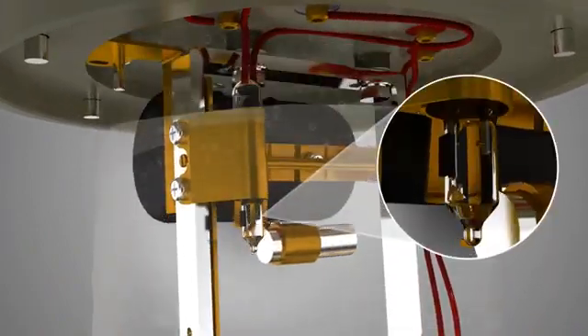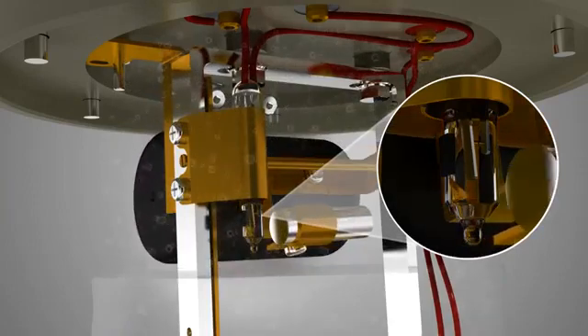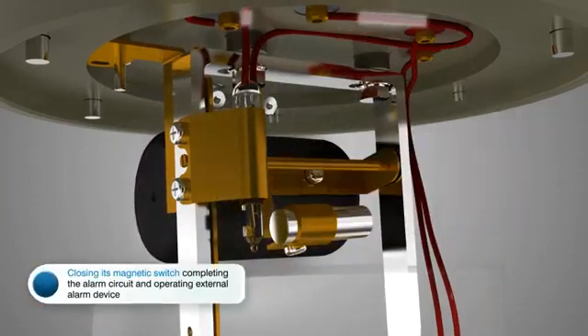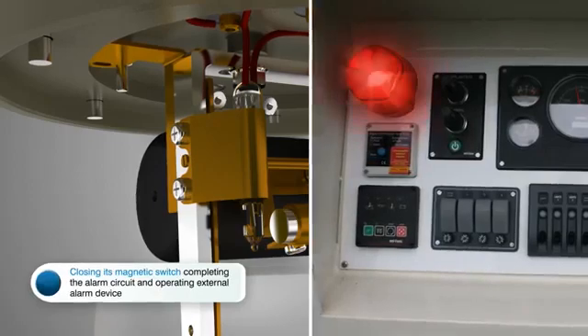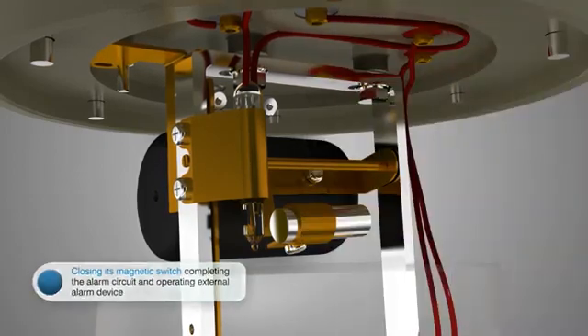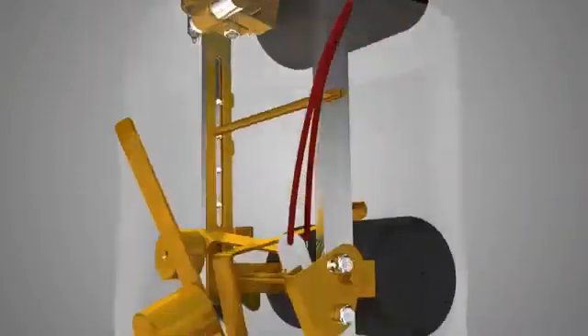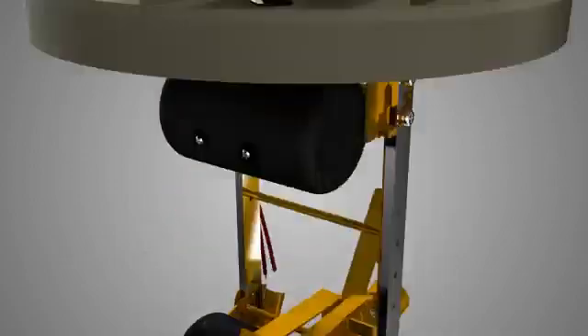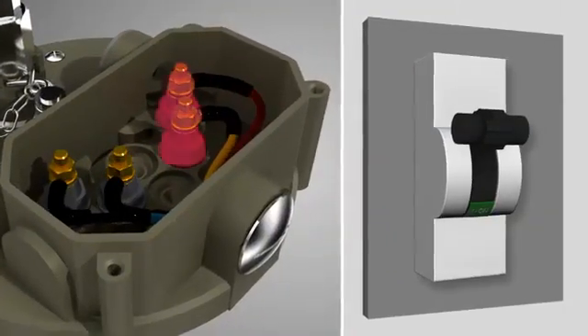The upper float falls down along with the oil level, closing its magnetic switch, thus completing the alarm circuit and operating external alarm device. If the oil level continuously goes down, the trip also operates.